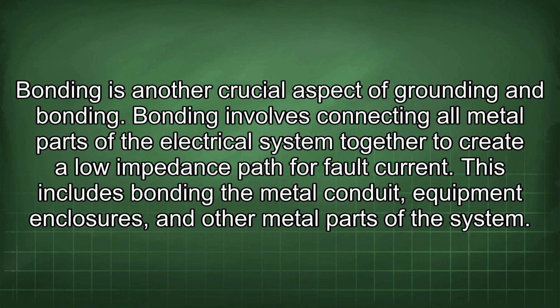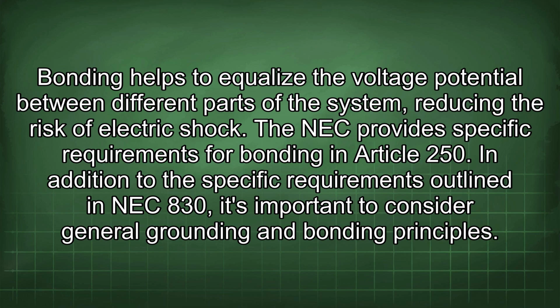Bonding is another crucial aspect of grounding and bonding. Bonding involves connecting all metal parts of the electrical system together to create a low impedance path for fault current. This includes bonding the metal conduit, equipment enclosures, and other metal parts of the system. Bonding helps to equalize the voltage potential between different parts of the system, reducing the risk of electric shock. The NEC provides specific requirements for bonding in Article 250. In addition to the specific requirements outlined in NEC 830, it's important to consider general grounding and bonding principles.